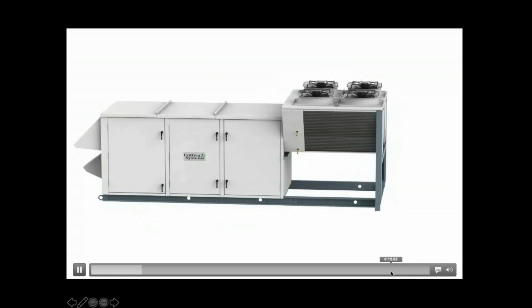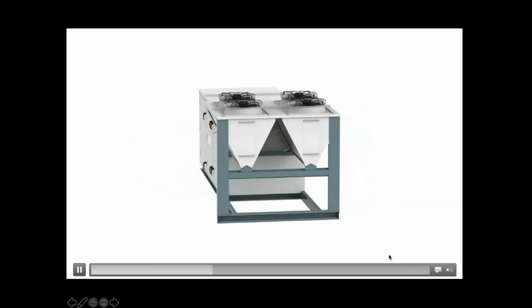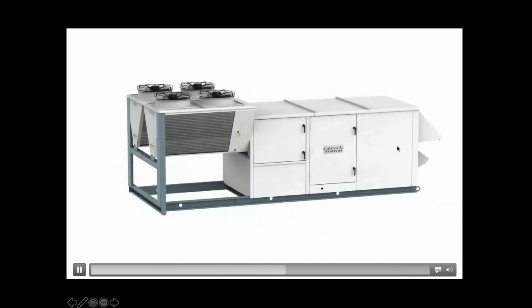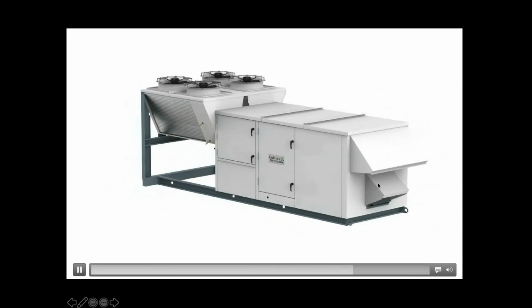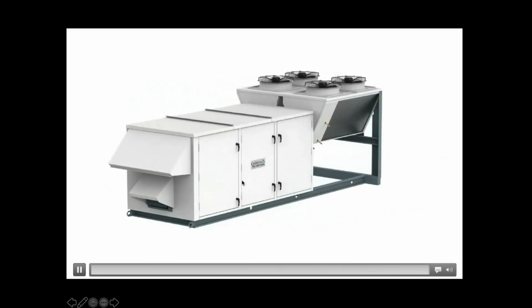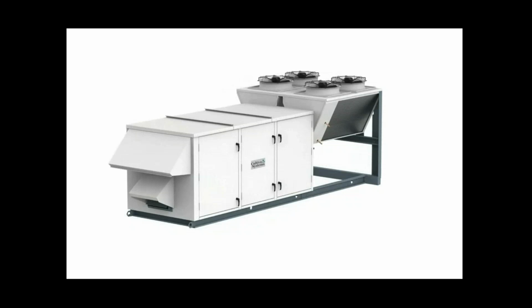Here's a picture of the unit. One of the things you will note about it is that it's shown with an outside air intake, essentially an economizer cycle. That is there. This unit was actually built by Addison. We had to take the Addison unit, which was a DOAS unit, and we gutted that unit to make room inside of that for our 6-row cooling coil. We've also got a 6-row space in there for a PCO air cleaner, which I'll get to in a minute. And then we've got our 2 hot gas reheat coils.